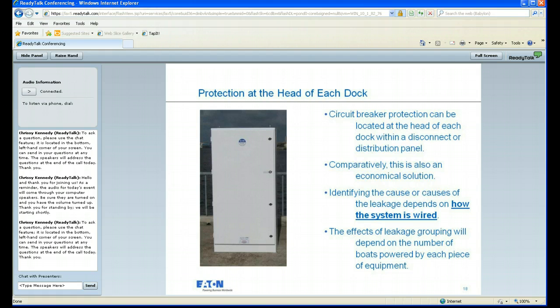Certainly. Thank you, Gary. That is definitely a point that needs to be on that slide, that it needs to be something other than a high primary voltage, whether you're being supplied with 600 volts or 480 volts or anything other than that. It needs to be applied on a 120/240 volt or 120/208 volt system to operate effectively. Now, the code language in 555.3 could be a little bit deceptive because it does say on the main. But depending on your design of the marina, you need to be careful about that. Certainly.